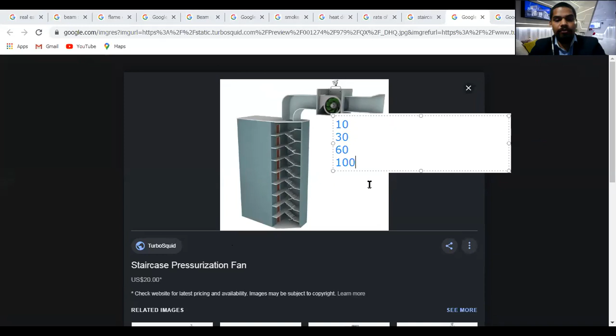So you have a four-speed setting: 10%, 30%, 60%, and 100%. These are the four speeds of the fan. So why is this speed control required? Practically, we notice that if you run that fan at 100% speed, the pressure of the staircase is too high. The person will not be able to open the door from the outside.